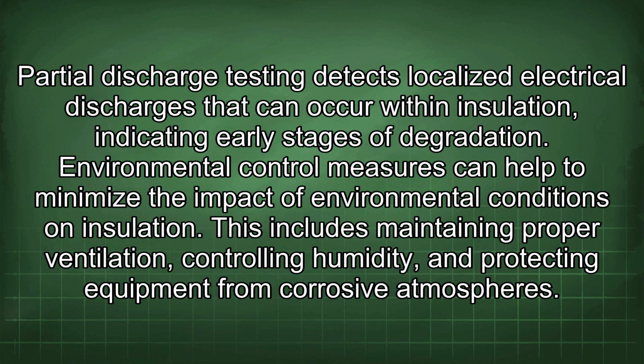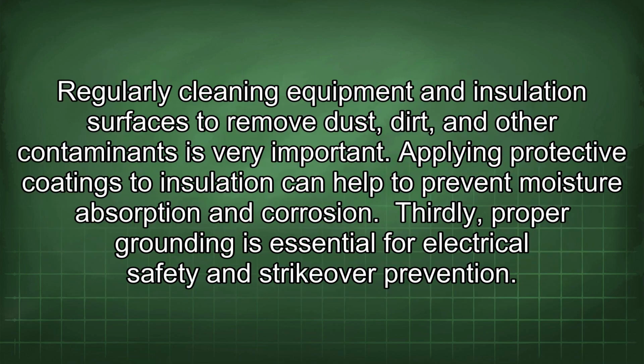Environmental control measures can help to minimize the impact of environmental conditions on insulation. This includes maintaining proper ventilation, controlling humidity, and protecting equipment from corrosive atmospheres. Regularly cleaning equipment and insulation surfaces to remove dust, dirt, and other contaminants is very important. Applying protective coatings to insulation can help to prevent moisture absorption and corrosion.